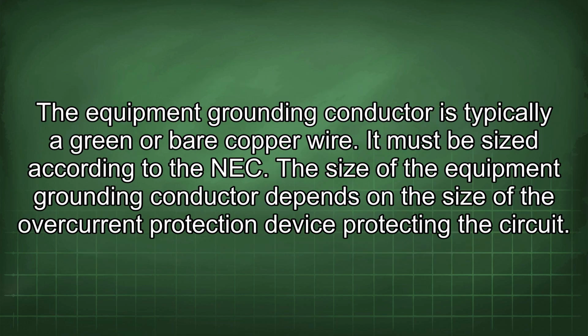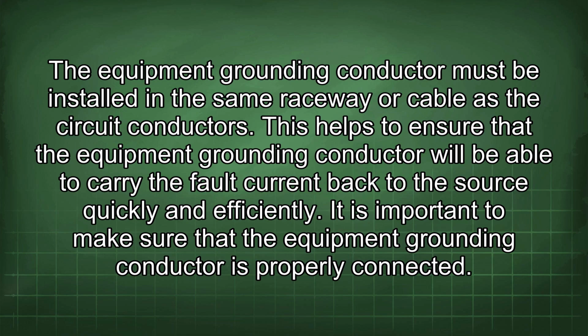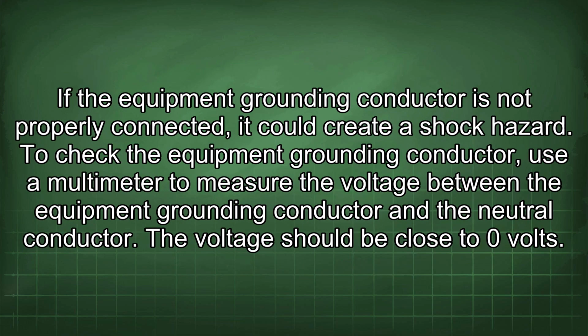The equipment grounding conductor is typically a green or bare copper wire. It must be sized according to the NEC. The size of the equipment grounding conductor depends on the size of the overcurrent protection device protecting the circuit. The equipment grounding conductor must be installed in the same raceway or cable as the circuit conductors. This helps to ensure that the equipment grounding conductor will be able to carry the fault current back to the source quickly and efficiently. It is important to make sure that the equipment grounding conductor is properly connected. If the equipment grounding conductor is not properly connected, it could create a shock hazard.